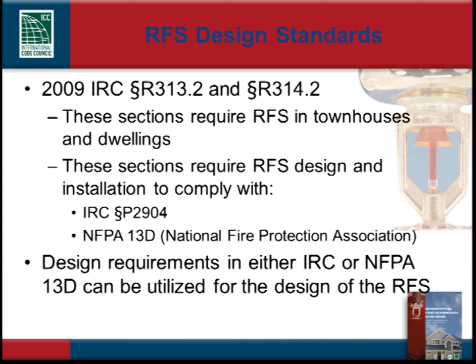These specific sections in the IRC — Section R313.2 and R314.2 — contain the requirements for residential fire sprinklers in dwellings and townhomes. These sections also specify that the design of the fire sprinkler system must conform to either IRC Section P2904, or the National Fire Protection Association Standard 13-D, installation of sprinkler systems in one- and two-family dwellings and manufactured homes, simply referred to as NFPA 13-D.